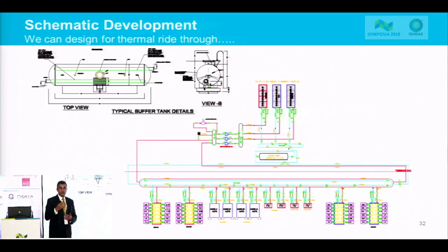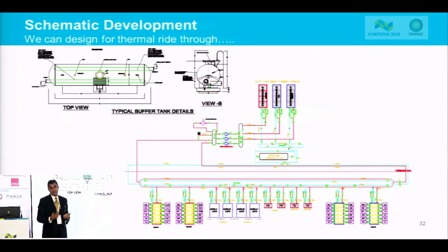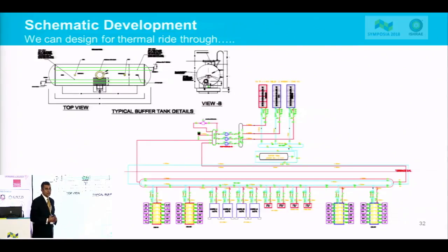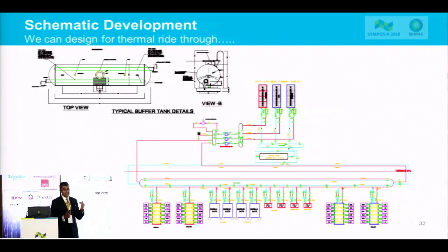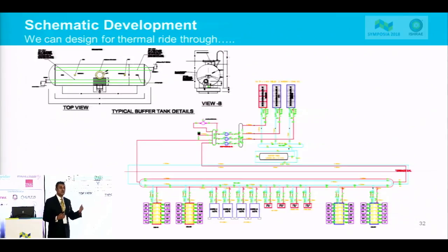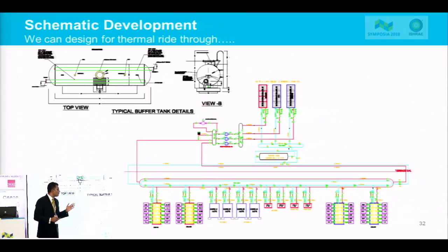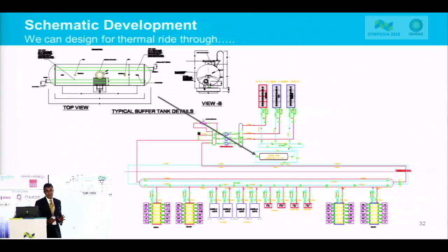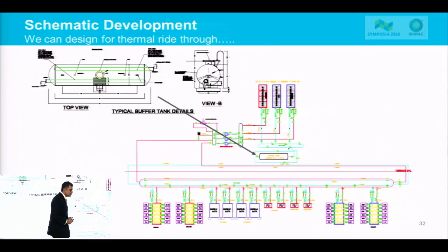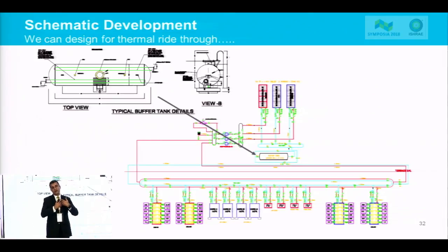So this is a typical scenario. We lose the grid, the on-site generators come on, and the cooling system is shut down. If it's a 5 kilowatt rack, in 4 minutes, you've lost the rack, right? So the pumps start, and all the chillers come on at the same time. You've got to ramp up the chillers and reduce the temperature within the data center as soon as possible. One of the strategies is using a thermal buffer system. It's like a UPS for a cooling infrastructure. These are just some of the various strategies, and with the increase in the thermal guidelines in the data center, as we increase the temperatures, there are also issues and strategies that need to be in place for humidity control.